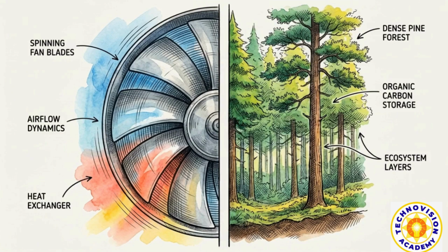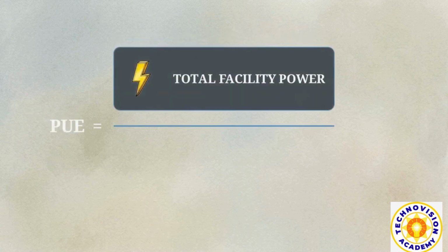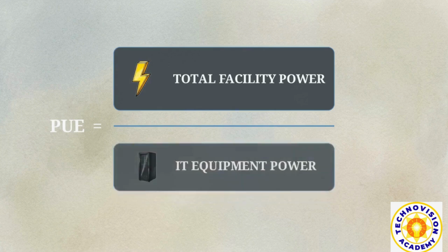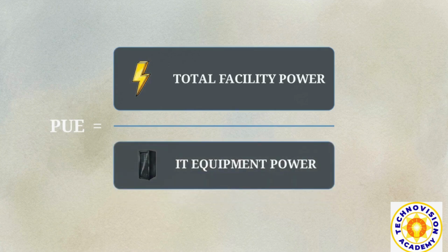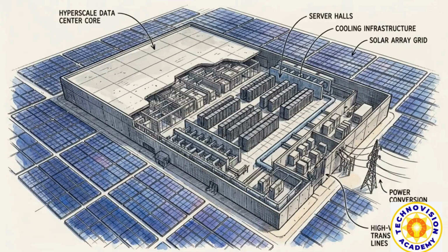Running these redundant cooling systems requires massive amounts of electricity, placing data centers in direct conflict with global sustainability mandates. This chart tracks power usage effectiveness, or PUE, the definitive metric engineers use to balance this conflict. PUE is calculated by dividing the total power entering the facility by the power actually consumed by the IT equipment, aiming for a target efficiency score of 1.0. Mastering this cooling infrastructure prevents imminent hardware meltdowns on the floor while dictating the environmental footprint of the digital economy.